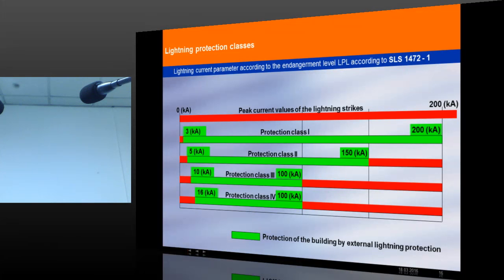See the first one, peak current values of lightning strike. In the earlier one which I have shown, 10 by 350, that is the shape of the current. But how many kiloamperes can it go? The first line shows lightning current can go to any value. The maximum recorded lightning is about 400 kiloamperes. But for the purpose of protecting a building, the maximum lightning current considered in the standard is 200 kiloamperes. Now the second line, 3 kiloamperes to 200 kiloamperes. Third one, 5 to 150, 10 to 100, 16 to 100. These are the various lightning protection levels explained.